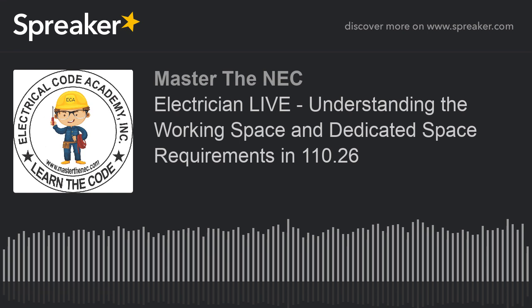Number 1, it says for equipment rated 1200 amperes or more and over 6 feet wide. Now, this is an important thing, the word and. And is very important because and is telling me that the first rule here is it has to be rated 1200 amperes or more. So we have a 1200 amp threshold. Okay, and again, remember, we're talking about the 2 entrances requirement now. Okay, it says that it has to be 1200 amps or more and over 6 feet wide. So if it was 1200 amps, but it was only 4 feet wide, then you wouldn't require the 2 entrances on either end of the equipment. You still have to have the adequate space, but you wouldn't require the entrance and egress at each end of the equipment. The and is very important to understand.